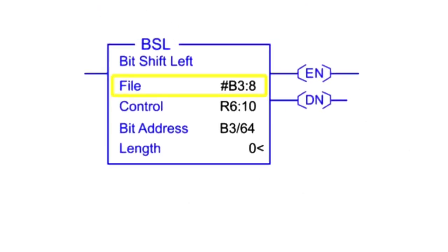The file field contains the address of the register that will be manipulated. The control field stores the status of the instruction. The bit address contains the source location for the bit being shifted into the register. Length is the number of bits. The actual length is determined by the application.